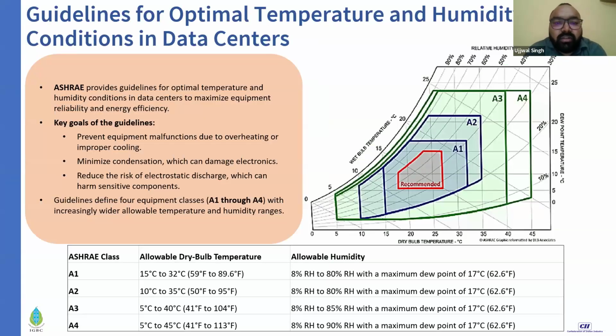And so now let's jump to the core of the topic. First, we will understand what kind of data center environment the cooling systems need to maintain. For this, we are referring to the ASHRAE guidelines. ASHRAE is the American Society of Heating, Refrigerating and Air-Conditioning Engineers, and they have suggested four classes, A1 to A4, where the limits of allowable dry bulb temperature and humidity go on increasing. So if you have an A1 server, you require more stringent controls on your cooling systems. Typically, the allowable range is 15 to 32 degrees Celsius, and allowable humidity is 8 to 80%, but with a maximum dew point of 17 degrees Celsius. The maximum dew point of 17 degrees Celsius has been put here to avoid possible condensation on any of the surfaces, which can cause a short circuit. And like this, we have an increasing bandwidth as we go from A1 to A4.